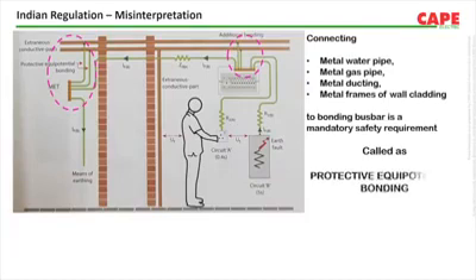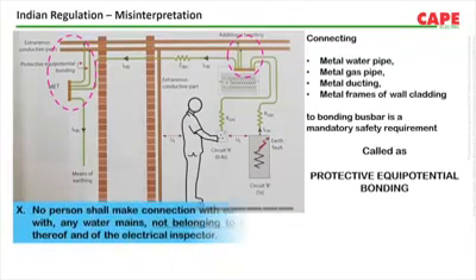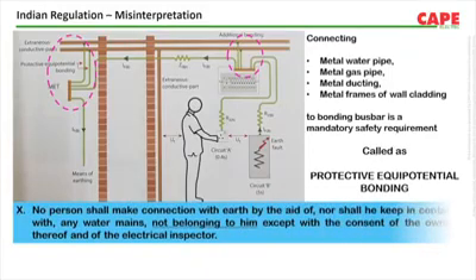In a given building, for example your building, there can be metallic installations which do not belong to you. For example, a metal water pipe belonging to the water supplier, or a gas pipe belonging to the company who supplies gas to a large building complex. These are metal installations not belonging to the owner of the building. While connecting a metal pipe not belonging to you to your protective equipotential bonding, you should inform the owner of that particular pipe, and you must get his permission or that of the respective electrical inspector. This is what is written in the IE Rules and in CEA regulation 41, point number X.